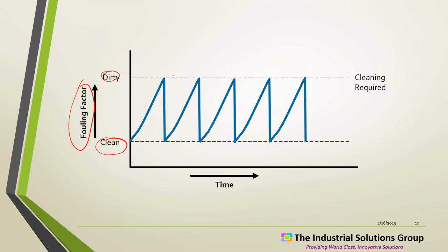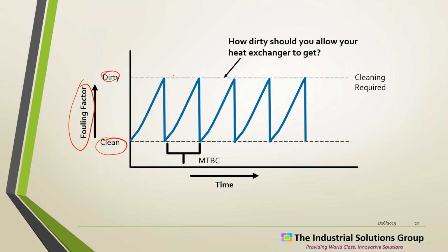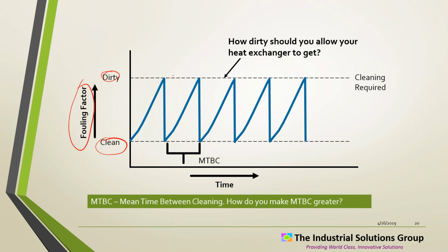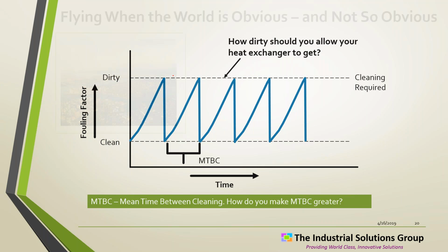How do you know when it's dirty? I've seen a lot of temperatures, but dirty requires a calculation. It requires a fouling factor, and I don't see that popping out of a lot of control systems. So you have the mean time between cleaning, and how do you make that greater? If we spread it out, obviously it's more runtime, more operation for the process.